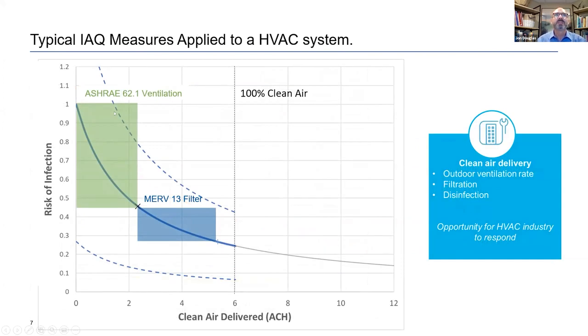So the first thing you always want to do is your ASHRAE 62.1 required ventilation. In this space, the ASHRAE ventilation gives you about 2.5 clean air changes per hour. So I added that in, and you can see we took our risk from 1 all the way down to about 0.45. Then the other recommendation, as Bill mentioned, is a MERV 13 filter. So we added in the clean air delivered per the MERV 13 filter, and you can see that takes the risk down from about 0.45 to like 0.28. So you can see there's quite a bit of risk reduction associated with just applying the standard 62.1 ventilation and MERV 13.